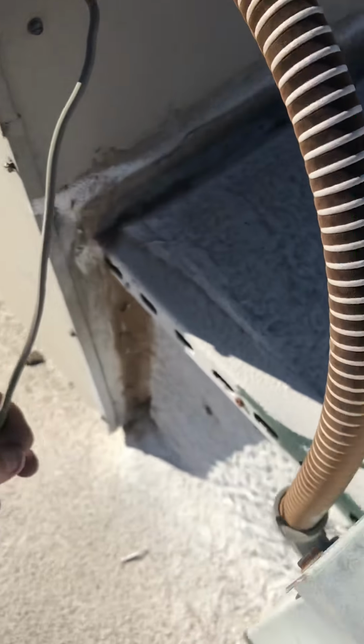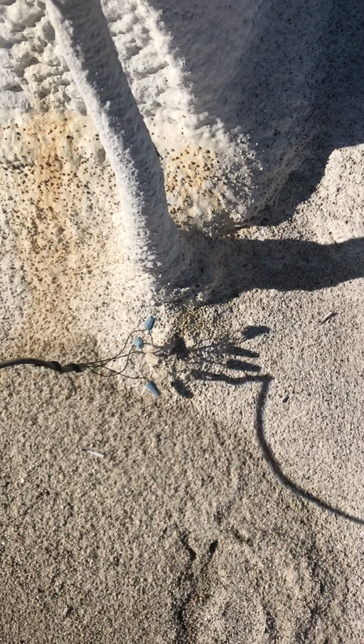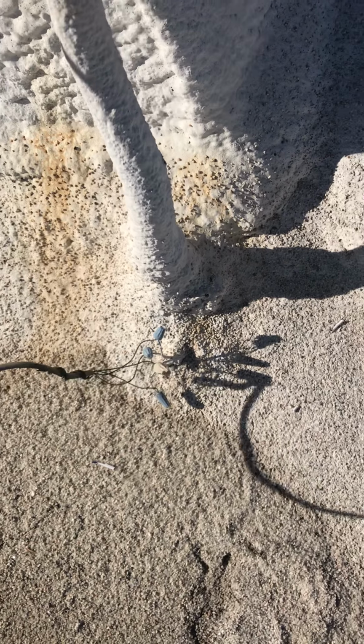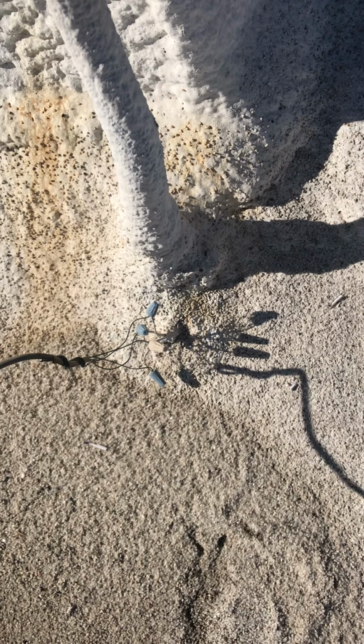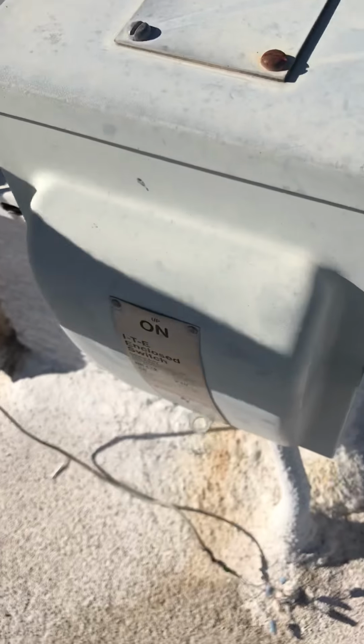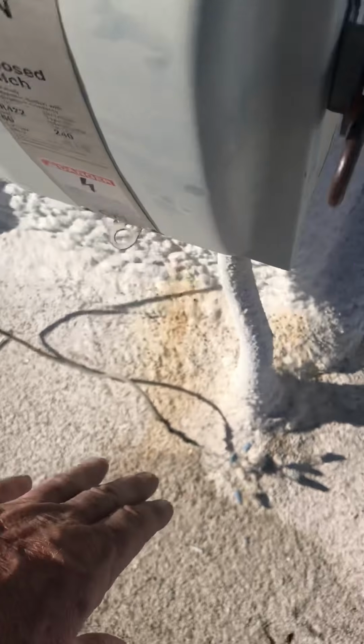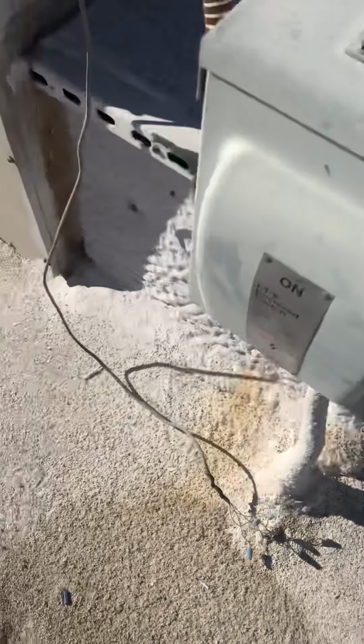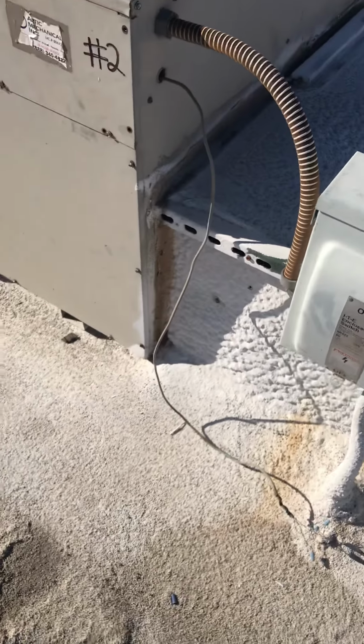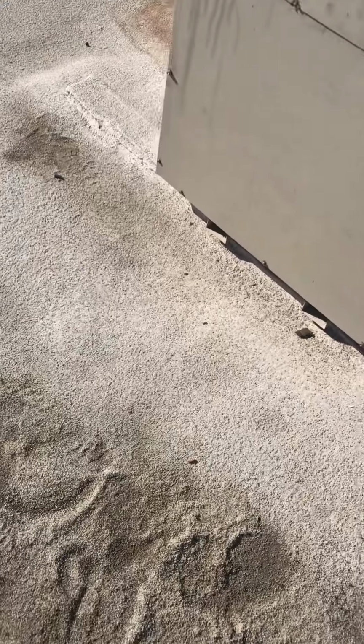The low voltage - this is actually code in Arizona - I can run my thermostat wire exposed. I'll most likely mount a box right there and take that thermostat wire from the box and run low voltage seal tight, probably 1/2-inch seal tight up to the new unit. That's actually code here in Arizona as far as leaving low voltage exposed with wire nuts. So I know a lot of guys work in different states, and that is completely to code.